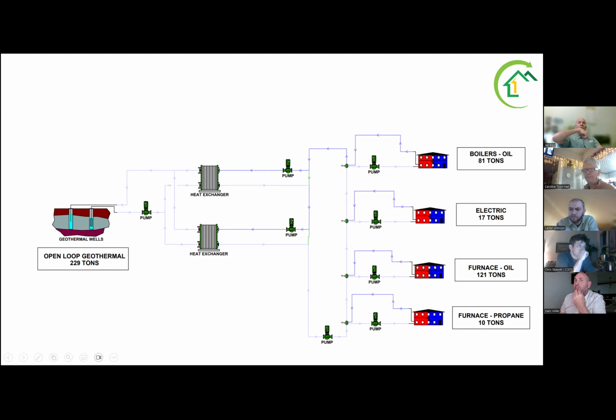The beautiful thing is these heat pumps are what we call extended range geothermal heat pumps. They operate happily at any temperature between 25 degrees, using a heat transfer fluid, and 110 degrees. They're completely within spec at those temperatures, similar to low ambient air source heat pumps. You'll just never actually hit those extremes, so we try to maintain the loop between about 40 and 90 degrees year round.